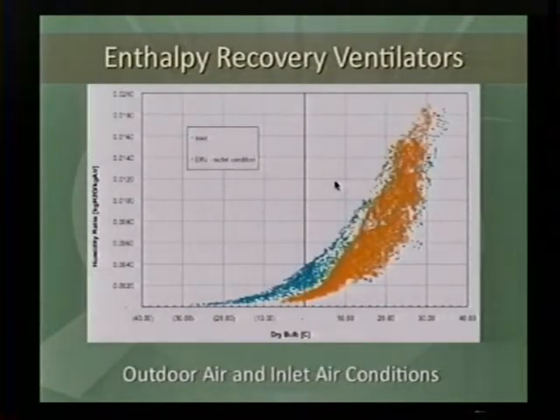And so an enthalpy ventilator does a much better job in the winter at recovering heat that would otherwise be leaving the building. In our climate in Wisconsin, it really doesn't do much at all in the summer, and you're better to actually bypass an enthalpy ventilator in the summer, because our outdoor conditions are so close to the indoor conditions that there's nothing to recover. Whereas the outdoor condition, where there is some humidity, when it's going down into the earth ducts that are running closer to the ground temperature of around 55 degrees Fahrenheit, there's a lot more pre-cooling that's going on there.